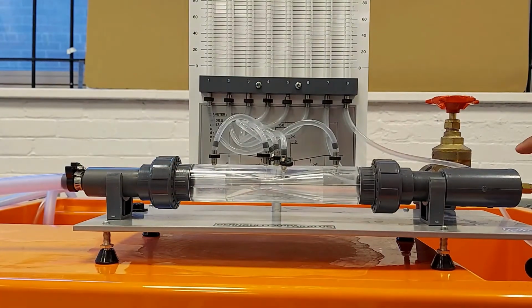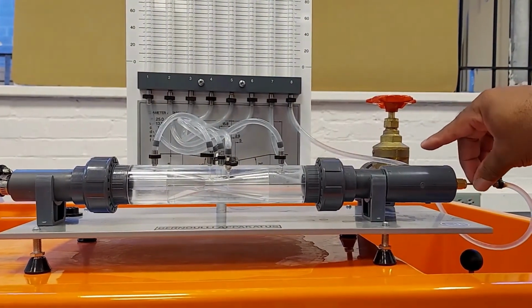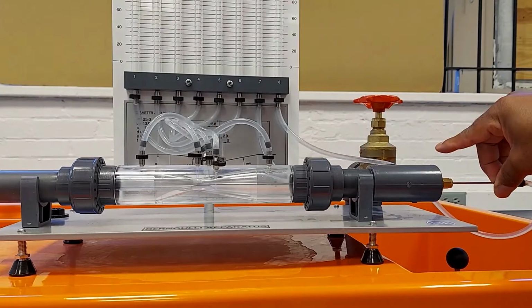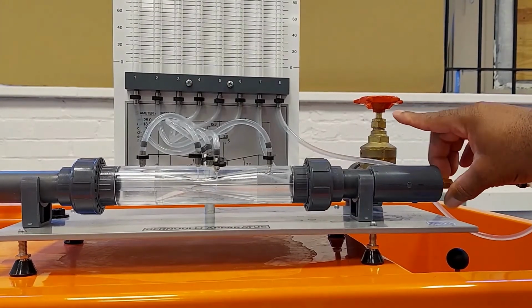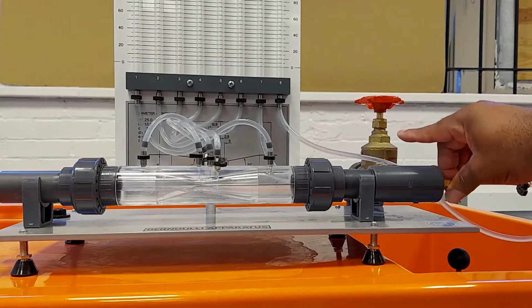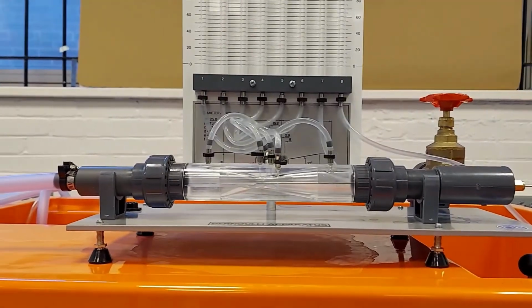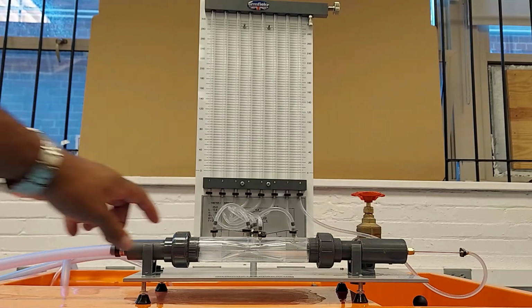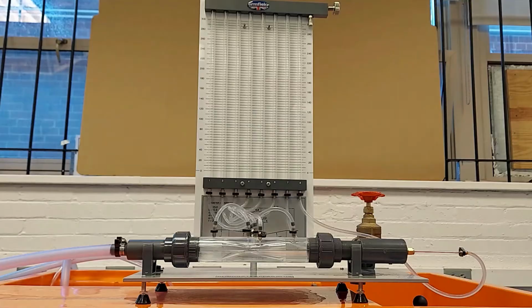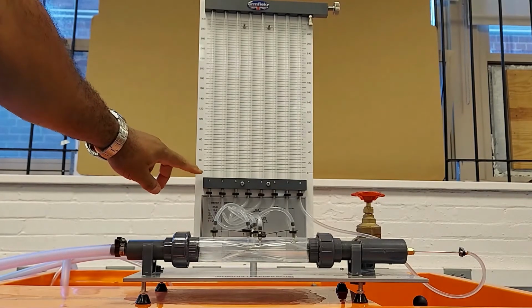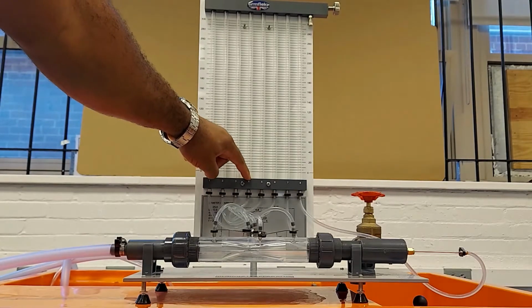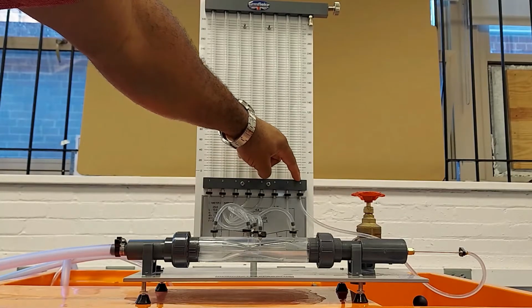This is done by releasing this screw and adjusting the tube, which gives us total head readings, to the tapping which you are taking readings from. These tappings, along with the total head probe, are all connected to a manometer bank, incorporating a manifold at the top with an air bleeding valve to remove air pockets in the system. The manometers are notated as H1, H2, H3, H4, H5, H6, H7, and H8.